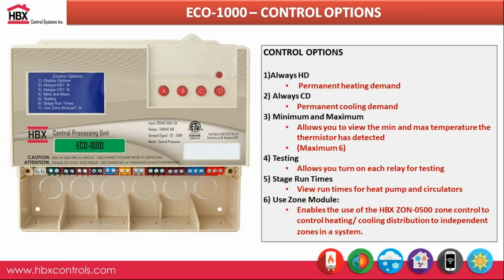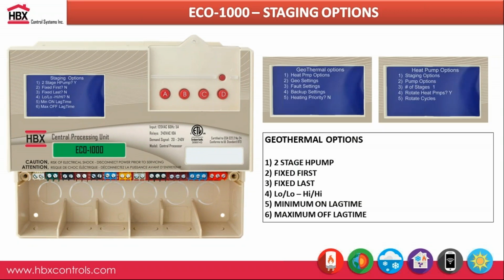So in terms of control options, if you were to go into our heat pump options, it's very straightforward. When you go into these heat pump options, you're simply selecting how many heat pumps you want to control. So if you had a total of anything less than 2, you're not using any expansion modules, you would just enter 2. If it's anything more than 2, it tells the controller that, hey, we are using expansion modules, and that will coordinate with those expansion modules.